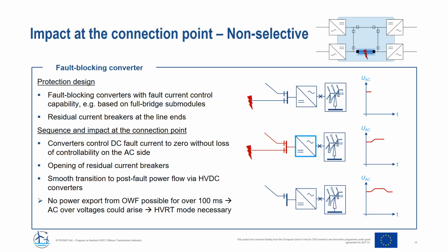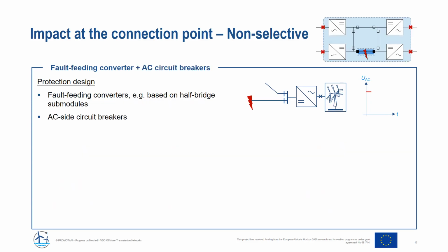However, during the fault clearing time, which might last over 100 milliseconds, no power export from the offshore wind farm is possible, so AC overvoltages could arise and a corresponding high voltage ride-through mode is necessary. For this last example, a non-selective strategy based on fault feeding converters, for example based on half-bridge submodules plus AC side circuit breakers, is presented. This is the strategy that is also used for the existing point-to-point links.